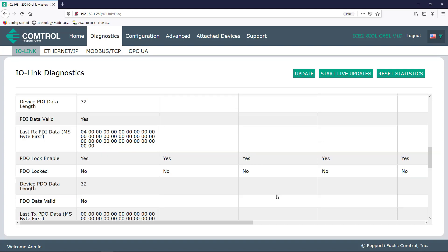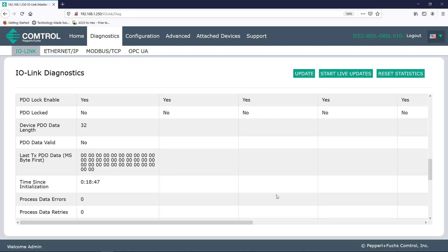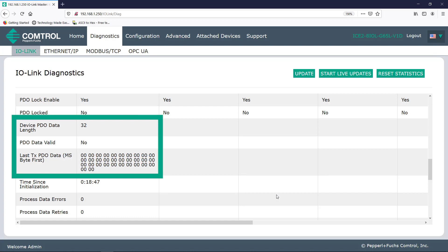And now let's talk about PDO or process data output. PDO lock enable. Just make sure that if a PLC is currently controlling the IO-Link setup, nobody comes in and changes a setting that they shouldn't using the web interface, for example, which if done could cause damage or worse to the machines. Here you see, yes, this feature is available, but PDO locked says no. So we're not currently locked out from making any changes. The process data output info on these next three lines are similar to the process data input already discussed above.